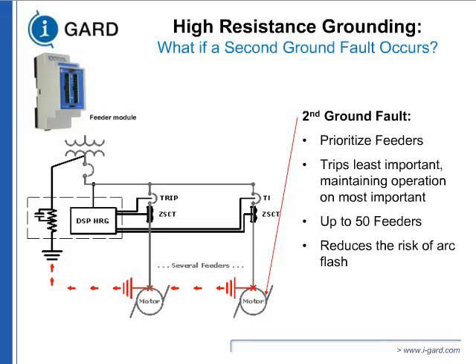Industry responded. That was a godsend to us. I wish it was there when I was an operating engineer. You can put in a prioritizing system. It tells you which feeder has a fault. If you imagine that you have 50 feeders, or 20 in a typical switchgear, and the first fault happens in unit 5, now you can prioritize that, hey, unit 5 is only priority 3 for me. If a fault happens in unit 4, which is a higher priority, you say, okay, I'll take number 5 down.